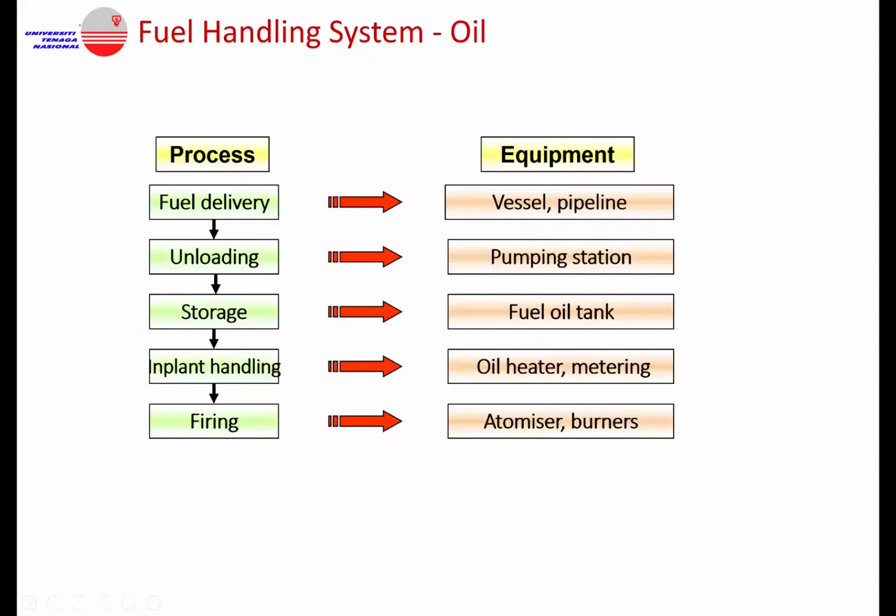One thing about handling of oil, since oil viscosity is relatively higher as compared to gas, it is important for us to ensure that the viscosity is always right. So this oil has to be consistently heated. That's why we have an oil heater and a metering station, just to make sure that it does not solidify. It has to be heated continuously to make sure that it can flow, before it is fired.